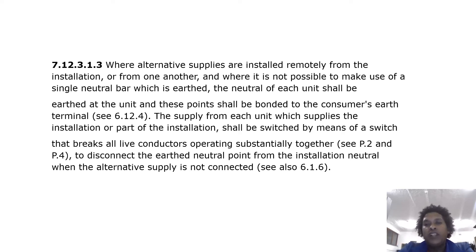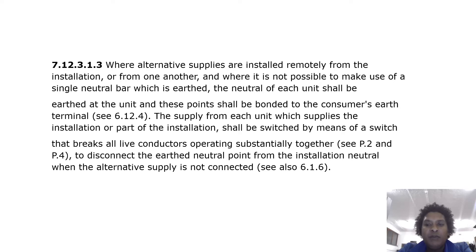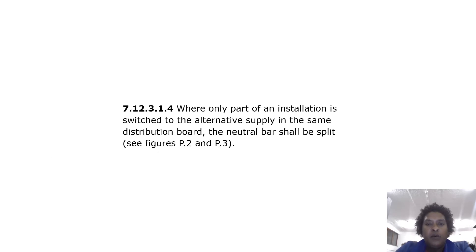Where alternative supplies are installed remotely from the installation or from one another and a single earthed neutral bar is not possible, the neutral of each unit shall be earthed at the unit and bonded to the consumer's earth terminal. The supply from each unit shall be switched by means of a switch that breaks all live conductors substantially together to disconnect the earth neutral point from the installation neutral when the alternative supply is not connected. Where only part of an installation is switched to the alternative supply in the same distribution board, the neutral bar shall be split.